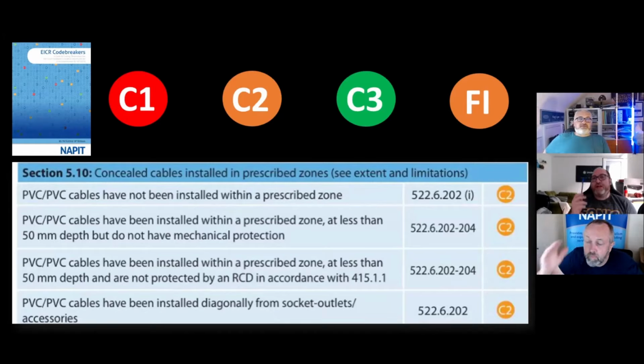But are you saying that's a reason not to select additional protection? No. Would you argue that in front of a judge? No, what I'm saying is the judge could argue that with me. So if the judge said, why didn't you do something about the RCD? I could say, as far as I was concerned there was an AC type RCD in there, but I wasn't aware there was an EMC or EMI issue where there was sufficient leakage or blinding of the RCD.